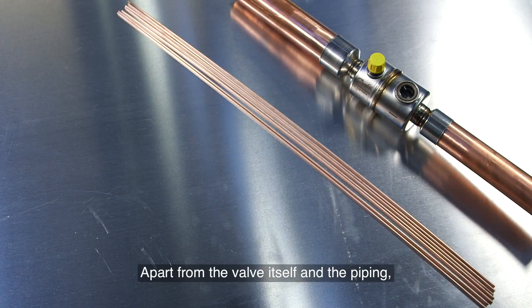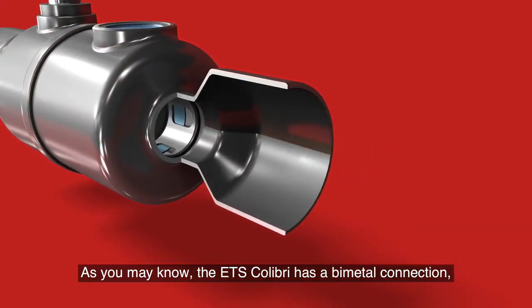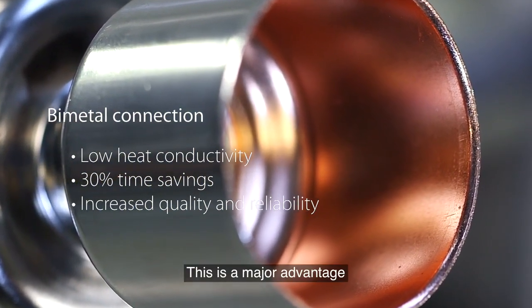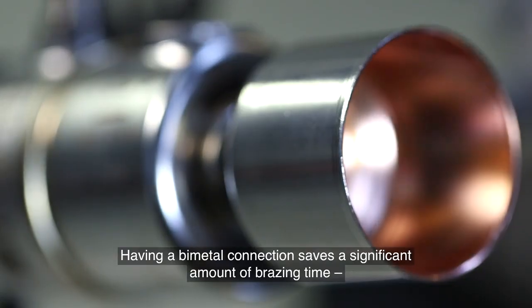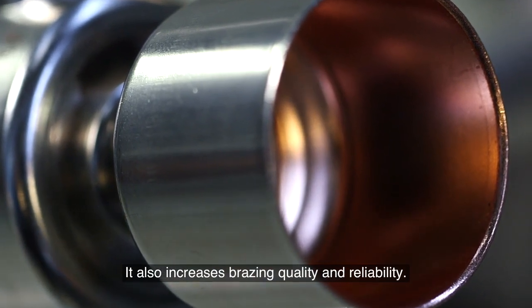Apart from the valve itself and the piping, it's important to use the correct solder material, brazing torch, and properly sized connections. The ETS Colibri has a bimetal connection with stainless steel outside and copper material inside. This makes the brazing process much faster thanks to the low heat conductivity of bimetal compared with pure copper connectors. There is no need for wet wrapping during the brazing procedure. Having a bimetal connection saves around 30% brazing time compared with a valve with a copper to copper connector, and also increases brazing quality and reliability.